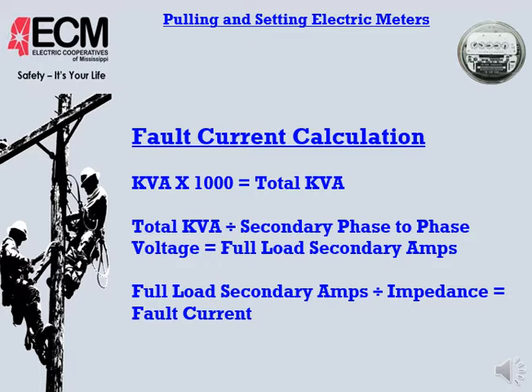If you're at a location, you take your kVA, you multiply it by 1,000. That gives you your total kVA. All right, you take your total kVA from the top line, and you divide that by your secondary phase-to-phase voltage, and that's going to give you your full load secondary amps. Well, secondary phase-to-phase voltage, usually at a residential application, that's going to be 120, 240. So we're saying phase-to-phase voltage would be 240 volts. We take that full load secondary amps and we divide that by the impedance of the transformer, and that's going to give us our fault current.